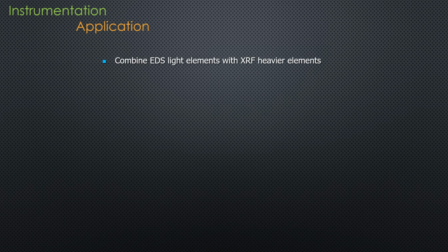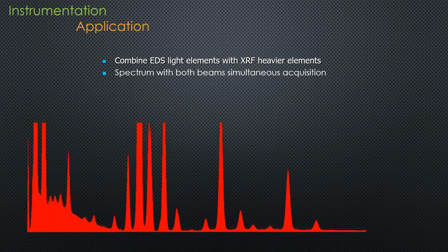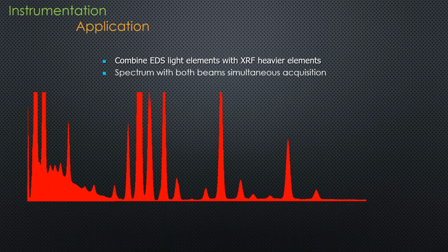Now let's talk about combining the two technologies. This is accomplished by turning on the electron beam up to around 3 kV and the XRF at 50 kV. By leaving the electron beam on, we excite just the lighter elements. We don't get much signal below 2 kV that we can use from XRF anyway. So by leaving both beams on, we can collect the E-beam data up to 3 kV, the XRF data up to 50 kV into one single spectrum.